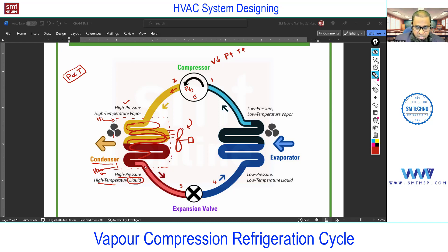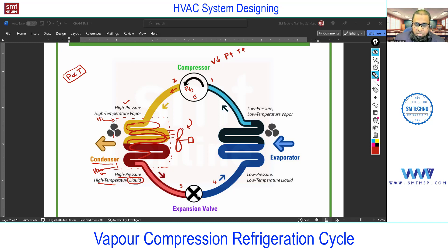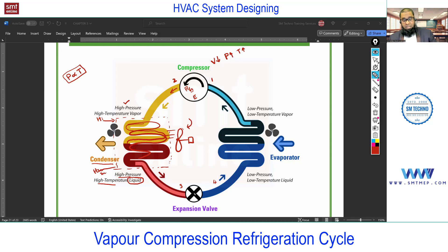Now, the outlet of the condenser has refrigerant in liquid form, still at the same temperature. We are interested to reduce the temperature, so this refrigerant in liquid form is allowed to pass through a device called the expansion device or expansion valve — it can be a throttling valve or a capillary tube. With the expansion device, the expansion process takes place. Expansion is the reverse of compression, so because of expansion, the volume increases and pressure decreases.